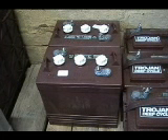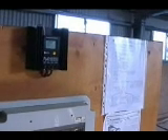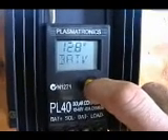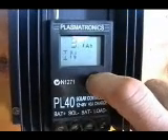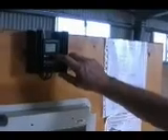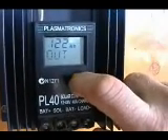If you'd rather be watching colour TV and maybe a few other appliances — perhaps a water pump — you'd look at a system a little bit bigger, probably costing about $3,000. For around about $3,000, you'd get two 80-watt solar modules, a frame to mount them on, a 250 amp hour battery bank, and a 200-watt inverter. The battery bank in this case is 250 amp hour — two 6-volt batteries wired up in series. This system also includes a 20-amp regulator with an LCD display, which will show you battery voltage, amps flowing in, amps being used, amp hours in for the day, amp hours used for the day, and a state of charge for the battery. You can also toggle through the history and it tells you all that information for every day for the last 30 days.